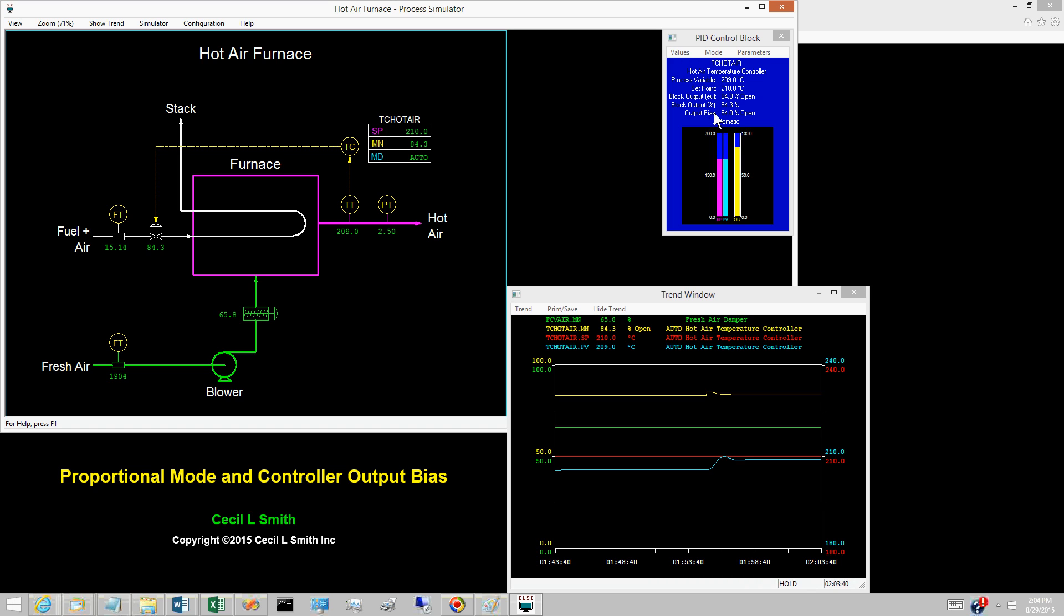The standard features of most commercial control systems will neither display the controller output bias nor accept values for it. The exception is for field-mounted regulators. The set adjustment is not the set point input to a comparator, but is the controller output bias.